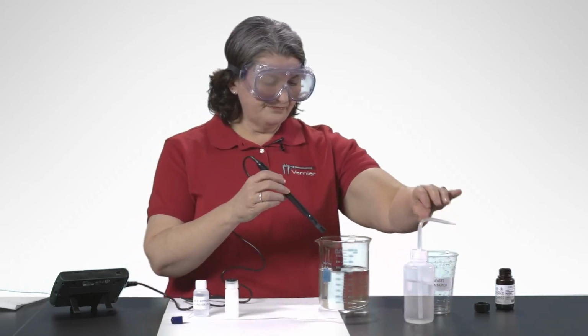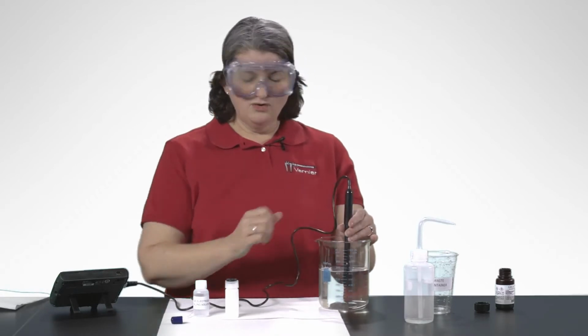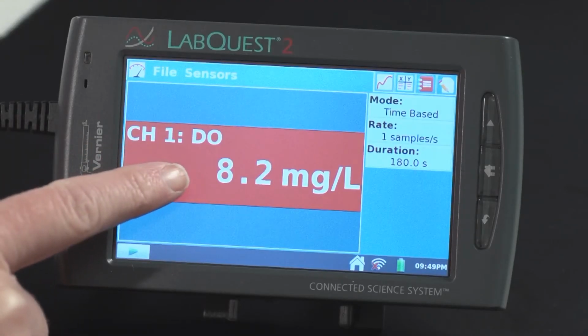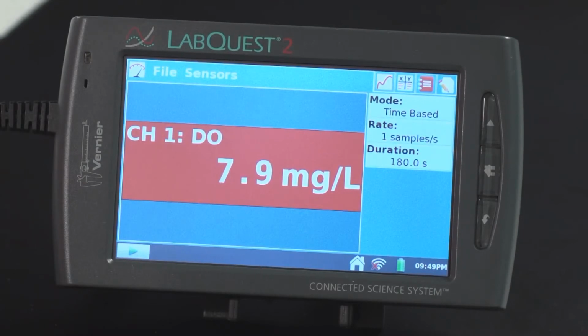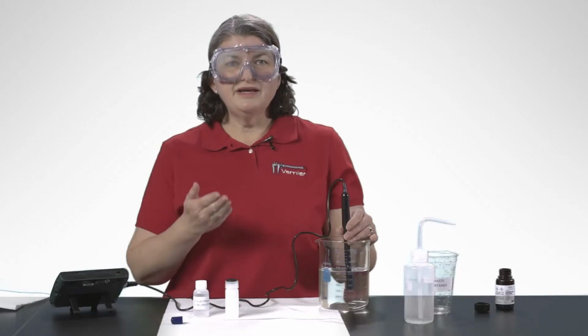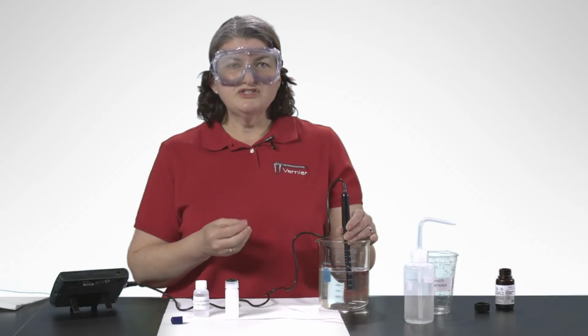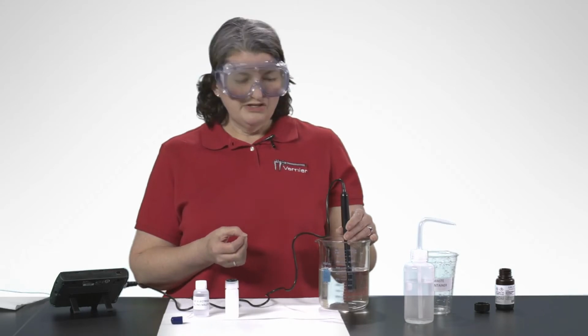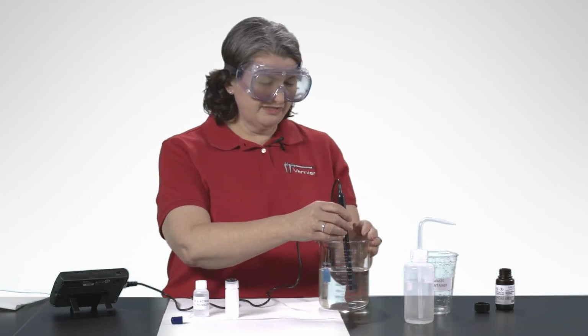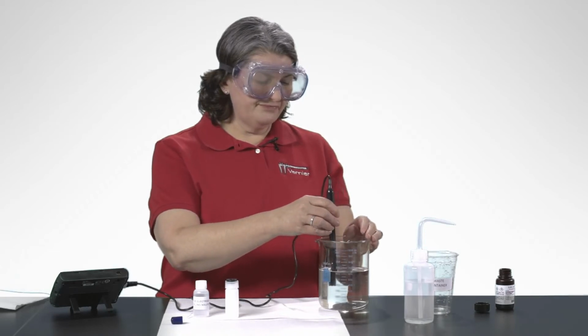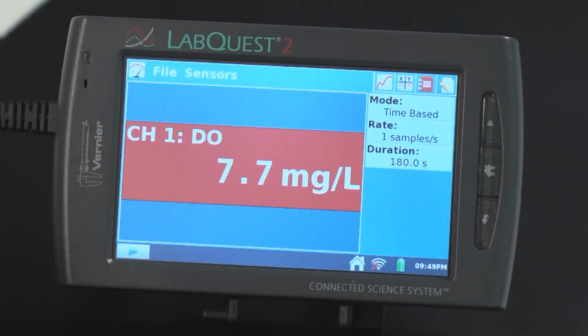So here's my water. If I put the sensor in and hold it still and watch my LabQuest screen, you're going to see the reading constantly drop. That's normal, and that's because right at the surface of the sensor, it is consuming a little bit of oxygen to make the measurement. So all I do, it's a negligible amount, so it doesn't matter as long as we are slowly stirring. And if we are slowly stirring and we watch the number on the LabQuest screen, it will eventually stabilize. Okay, so it looks like we have 8.1. That's our dissolved oxygen from my sample.